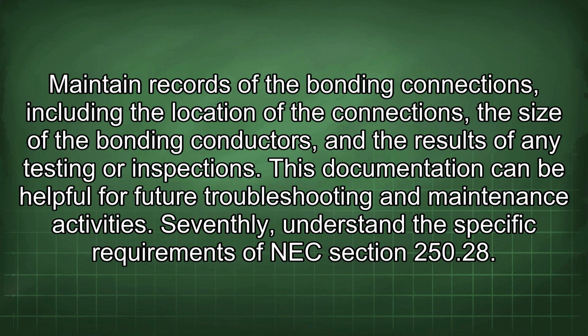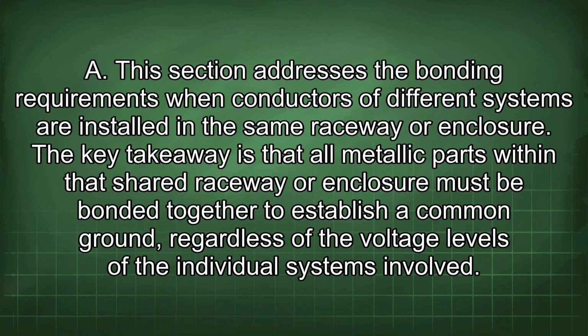Seventhly, understand the specific requirements of NEC Section 250.28(A). This section addresses the bonding requirements when conductors of different systems are installed in the same raceway or enclosure. The key takeaway is that all metallic parts within that shared raceway or enclosure must be bonded together to establish a common ground, regardless of the voltage levels of the individual systems involved.